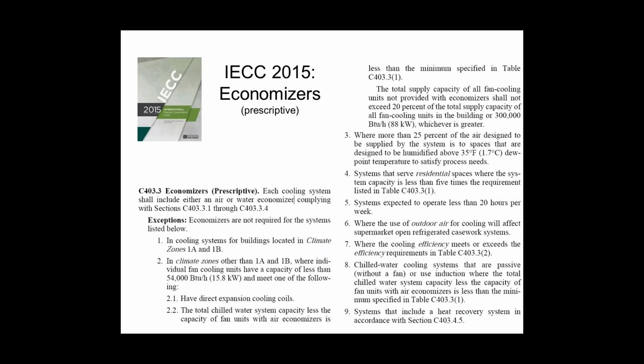This is the specific section that says when you need an economizer, and specifically for us in climate zone 5A, which is Chicago and the suburbs and so forth, where most of you guys are from, 54,000 BTUs and up is when you have to have an economizer. So this is 4.5 tons basically and up. This is not just for rooftops. This is all cooling systems. So if you got a split system, if you put a residential furnace and condensing unit in a commercial building, guess what? If it's 4.5 or 5 tons, you got to put an economizer on that split system. This is less stringent than the old number, which was 33,000 BTUs. So this new one went up a little bit, so you don't have to do it in quite as many scenarios. So now it's 4.5 tons and up, basically.